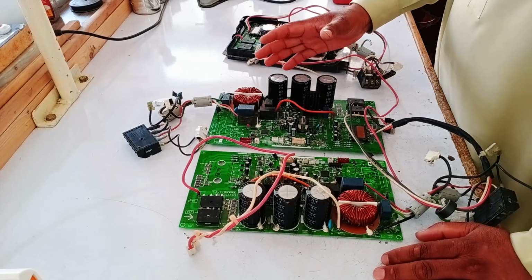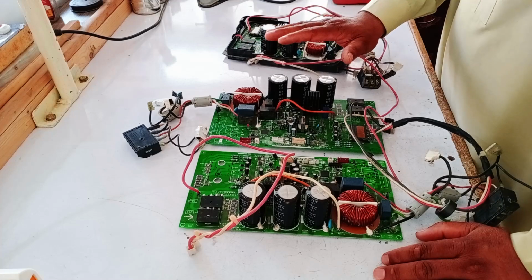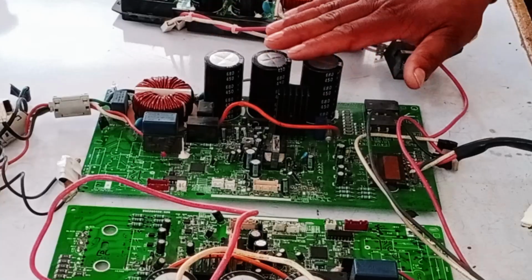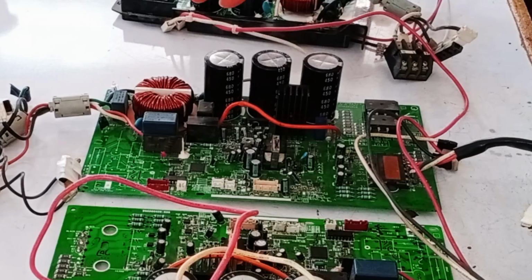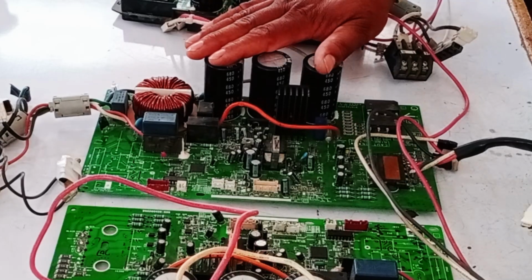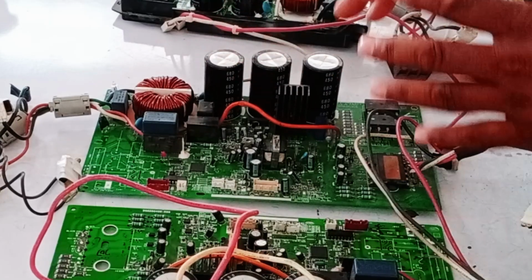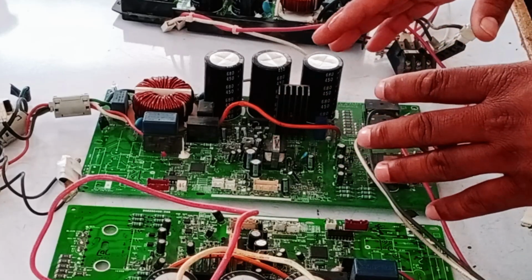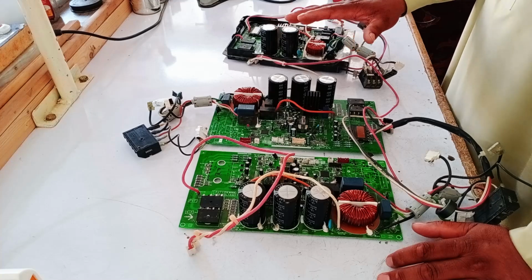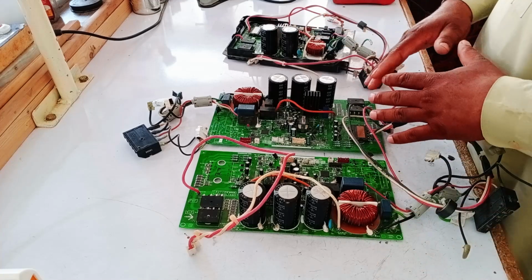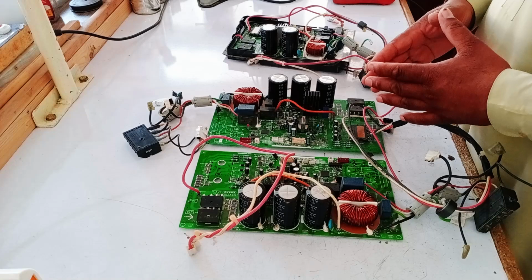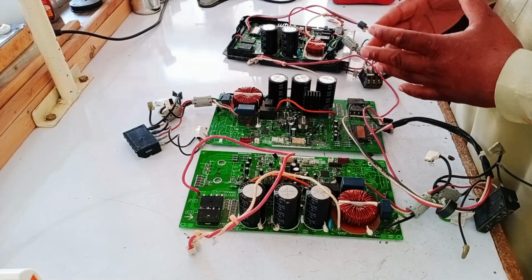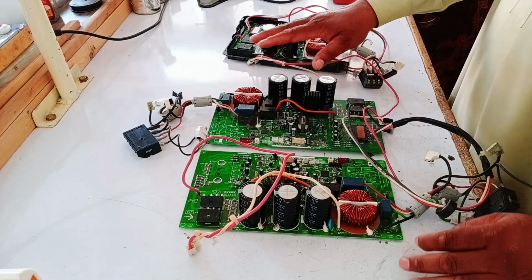In that case, turn off the unit for about 10 to 15 minutes. The reason for this is that capacitors store charge, and when the unit is turned off, the stored charge is discharged, which clears the unit's memory. When you turn the unit back on, there is a chance that it will start working normally. Now, if after following these steps the unit is still showing an error and not working properly, it means that a fault has developed in the unit after the fluctuation, which is now a permanent fault.